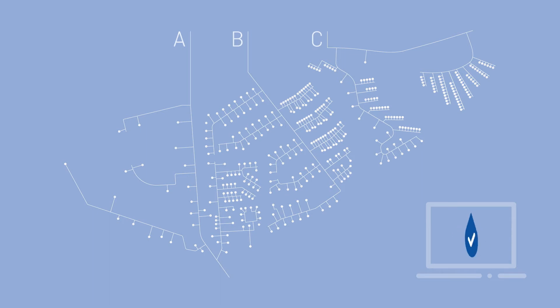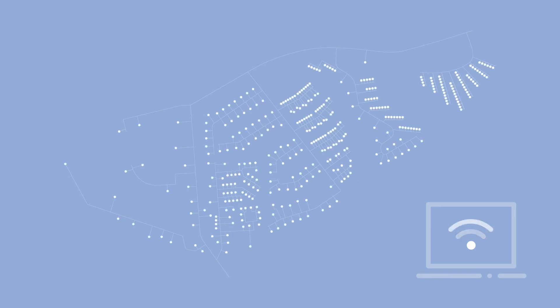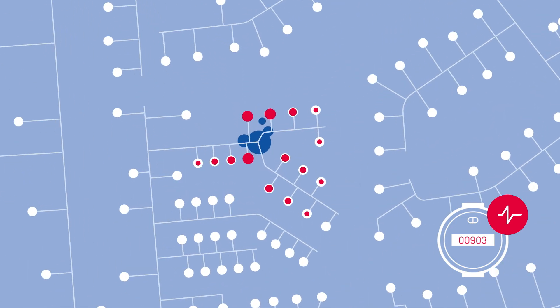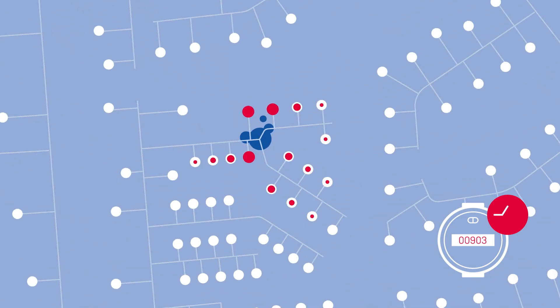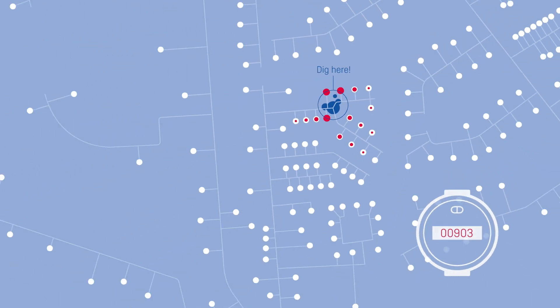But why stop there? Now you can activate your entire network and let every smart meter work for you to help locate leaks, acting like a fine mesh network of noise loggers. The meters listen to the distribution lines and the service connections, using sound waves to detect leakages. This will help focus your manual leakage detection significantly and ensure that you don't dig in the dark, but where and when it is necessary.